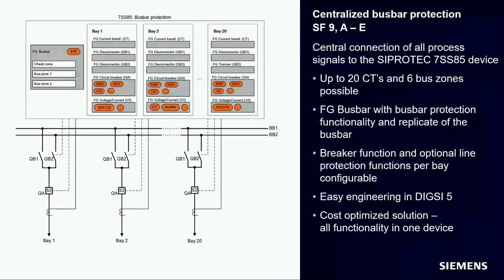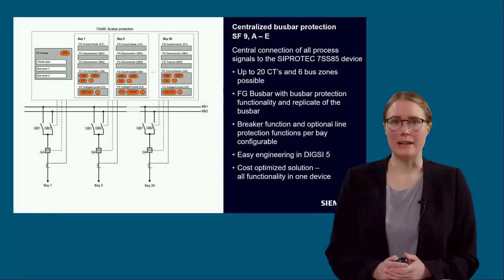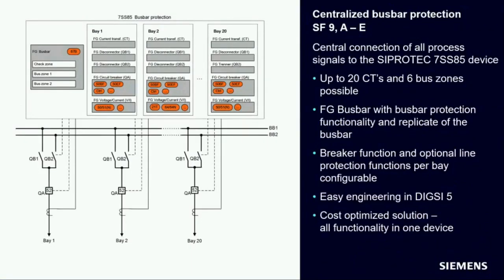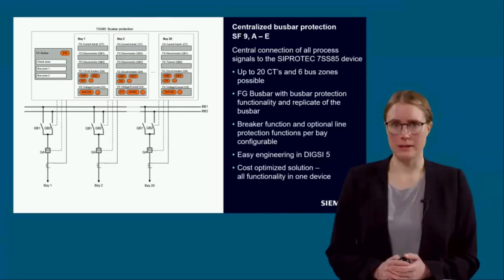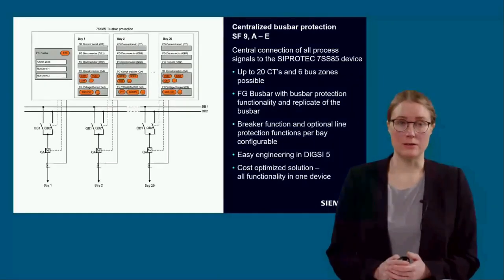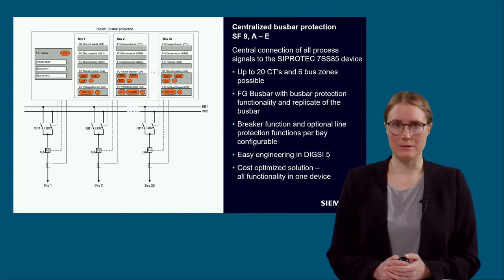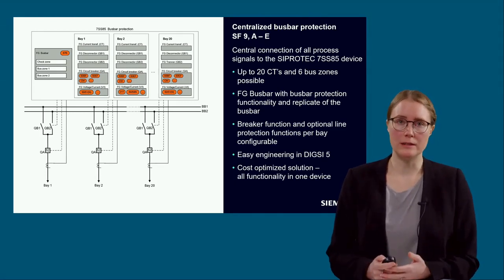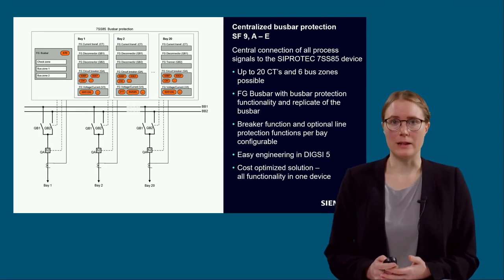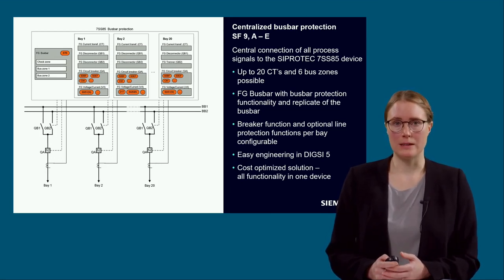For each bay, there is a bay including all the elements that are physically actually there. So there are, in this case, a function group current transformer, 2 function group disconnector, a function group circuit breaker, and a function group voltage current 3-phase if additional backup protection functions are required. In the function group circuit breaker, some additional functionalities like the circuit breaker failure protection or end fault protection are included. The engineering process in DIGSI 5 is to draw the single line diagram as it is shown here, create the 7SS85 with all these function groups and elements and functions you want to use, and then connect them to the elements in the single line editor.